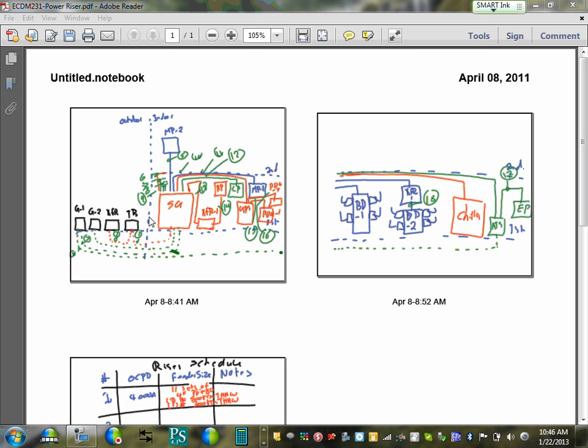I'm assuming you're going to have somebody come in and talk about the UPS. Is this a PDU? These are PDUs. So that would be a 480 UPS system, and then that feeds 480 to 208 PDUs. The PDUs are basically a cabinet that has a transformer and the panel all incorporated into it, plus monitoring and alarming for anything that's going on. It's a box with a transformer and a panel, but they have smarts so that you can monitor the load on each breaker in that panel, and any alarming that you need.